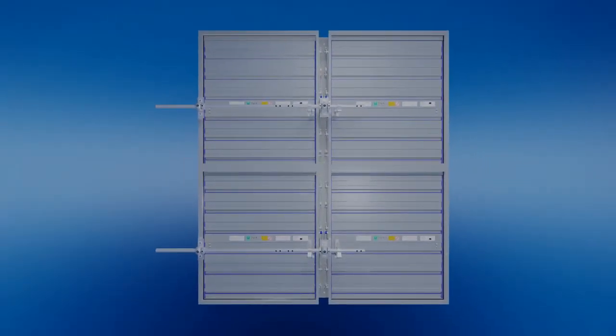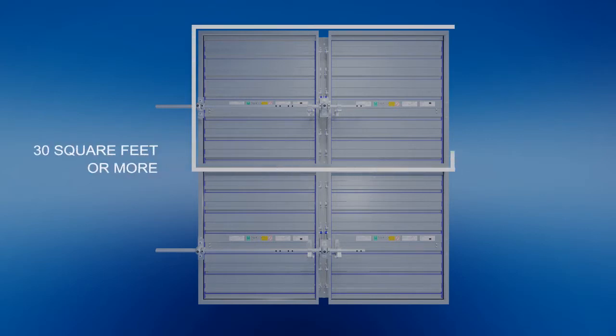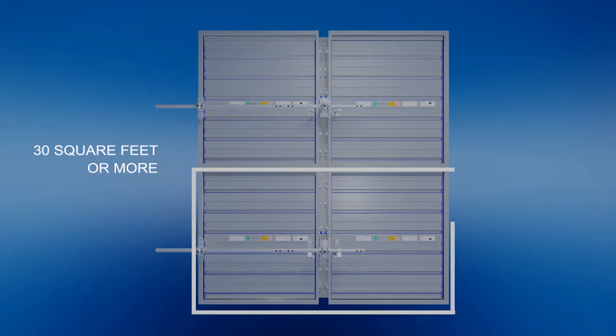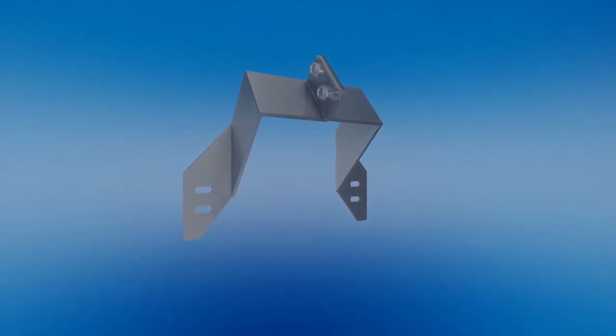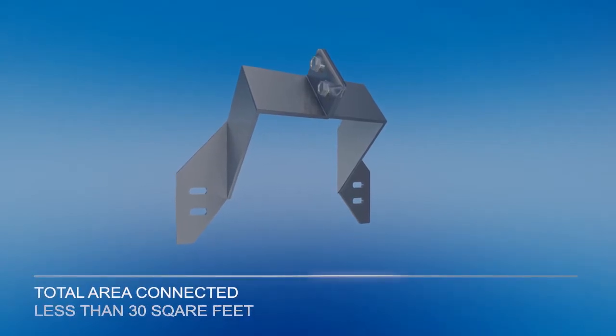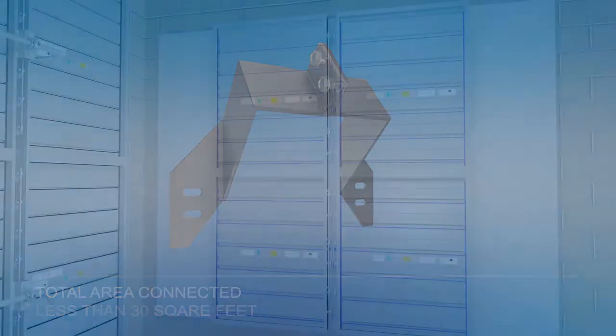Jackshafts are required whenever 30 square feet of damper surface area or more are to be actuated from any one motor location. Jumpers may be used to link sections if the total area connected is less than 30 square feet.